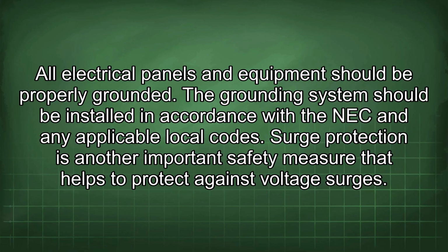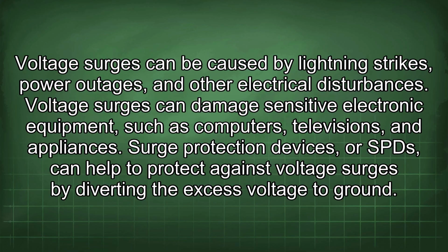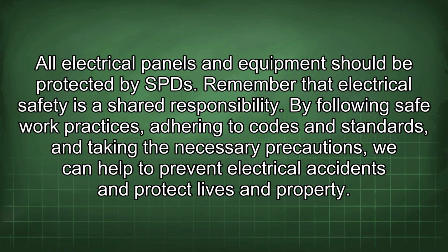Surge protection is another important safety measure that helps to protect against voltage surges. Voltage surges can be caused by lightning strikes, power outages, and other electrical disturbances. Voltage surges can damage sensitive electronic equipment, such as computers, televisions, and appliances. Surge protection devices, or SPDs, can help to protect against voltage surges by diverting the excess voltage to ground. All electrical panels and equipment should be protected by SPDs.